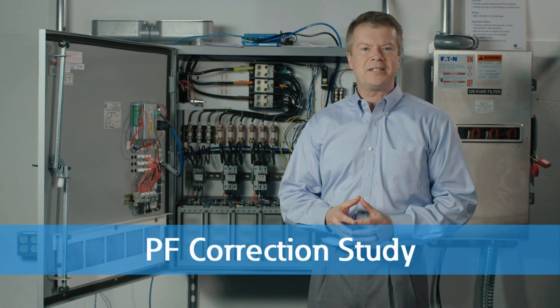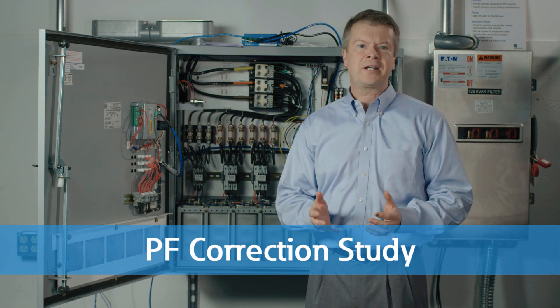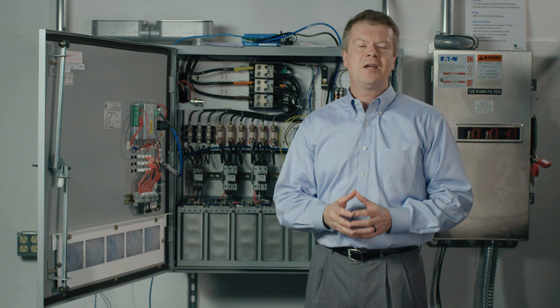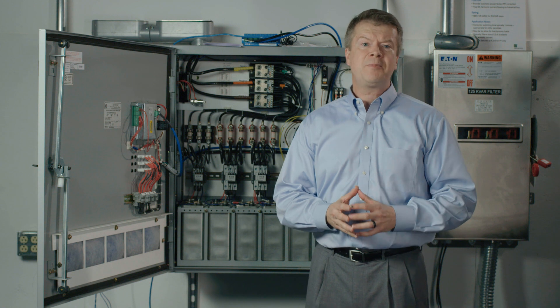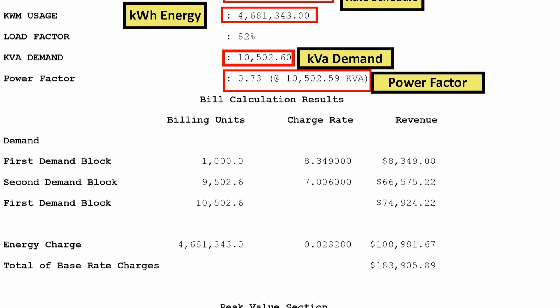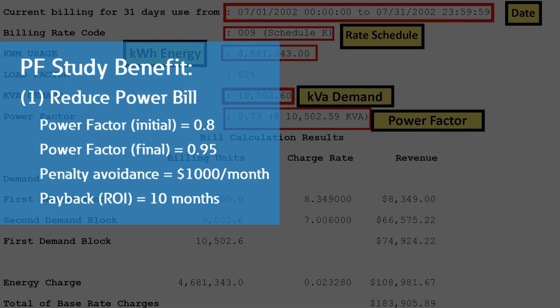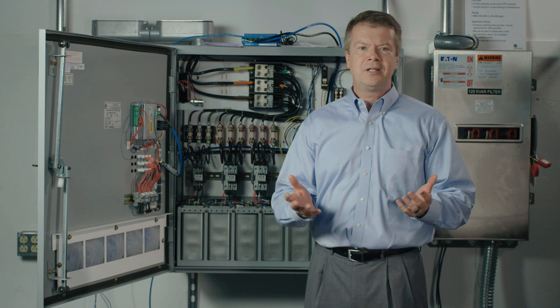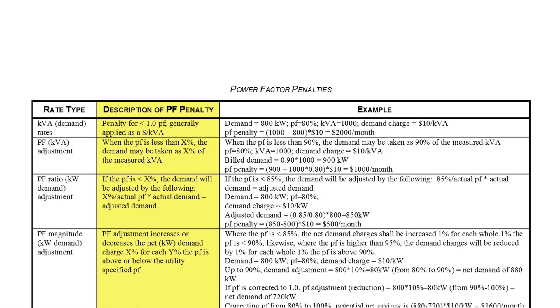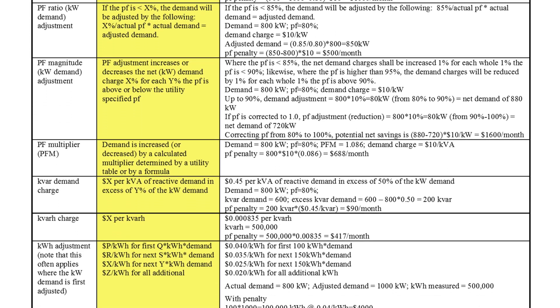Using the load flow model as a base case, a power factor correction study can be done to determine where capacitors or other power factor correction could be applied. Optimizing reactive current flow by correcting the power factor can save you money. The benefits of power factor correction studies are twofold. First, it can show you ways to reduce your energy bill. For large commercial or industrial customers, utilities often impose a power factor penalty on a bill. This may be a simple multiplier or a very complex calculation depending on the utility. There are almost as many types of power factor correction penalties as there are utility companies, but the payback may be as short as a few months.